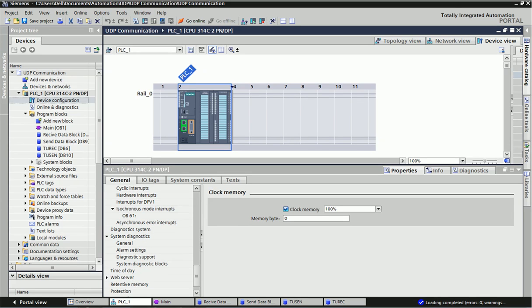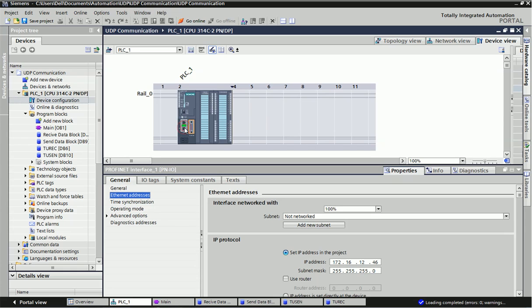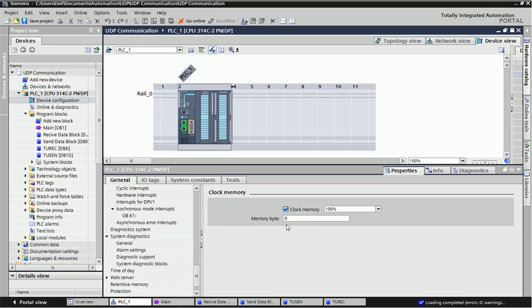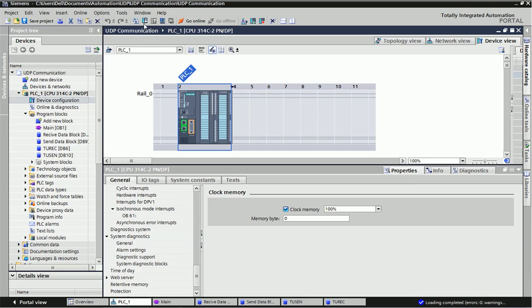Here we have Siemens TIA Portal software and I have configured a Siemens S7-300 CPU. This is the S7-300 PLC. First we will set the IP address — I have given 172.16.12.46. The second thing we will do is enable the clock memory in the PLC. After assigning the IP address and clock memory, we will download the PLC.